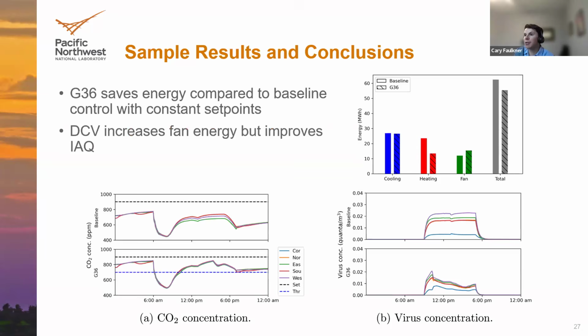We did see an increase in fan energy, and this is related to the demand controlled ventilation, or DCV, which was part of the controls and increases ventilation based on the CO2 measurements in the zones. In particular, we saw that this would happen quite often towards the end of the day, as you see in the bottom plots. That bottom plot shows the set point, or the band, in which the demand controlled ventilation might increase based on the CO2 measurements. As CO2 increased within the zones, maybe around 3 p.m., after people had been in the office for a good portion of the day, the demand controlled ventilation would respond and increase the ventilation to the zones. That would improve the indoor air quality, both in terms of the CO2 levels and the simulated virus concentration levels, as it pushes more air through, but it would lead to more fan energy usage.